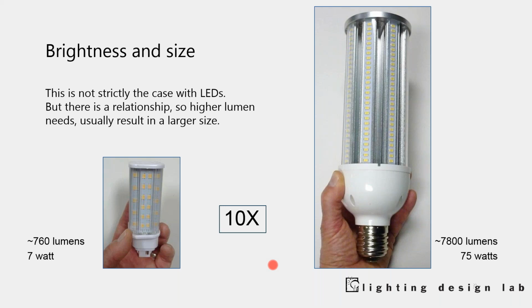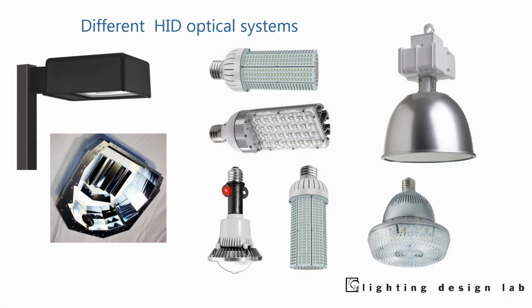So there's a variety of types of products for HID retrofit to screw in that we're seeing on the market. And sometimes if it's horizontal, they have light coming out just one side, or if it's more like a little spotlight, or if it's omnidirectional, they try to be omnidirectional. None of them work that great in my experience.